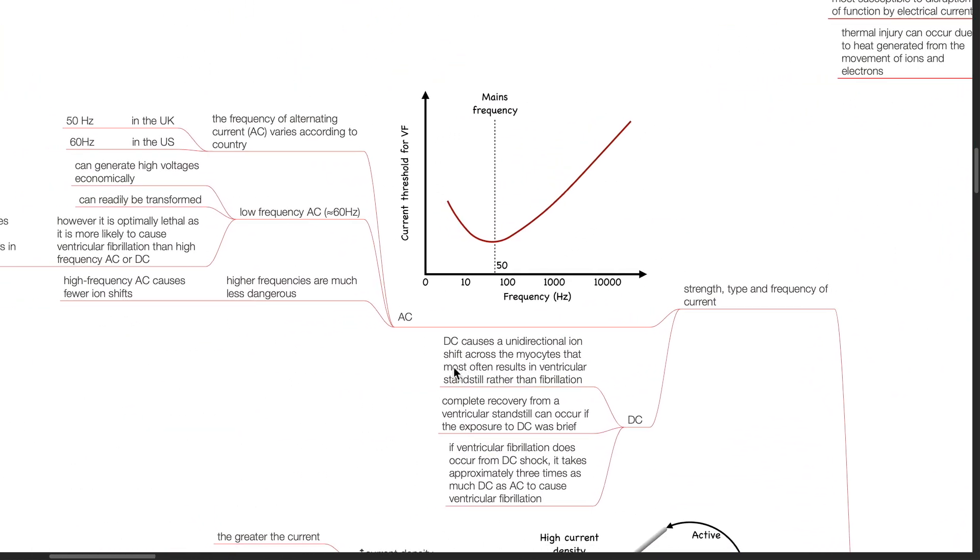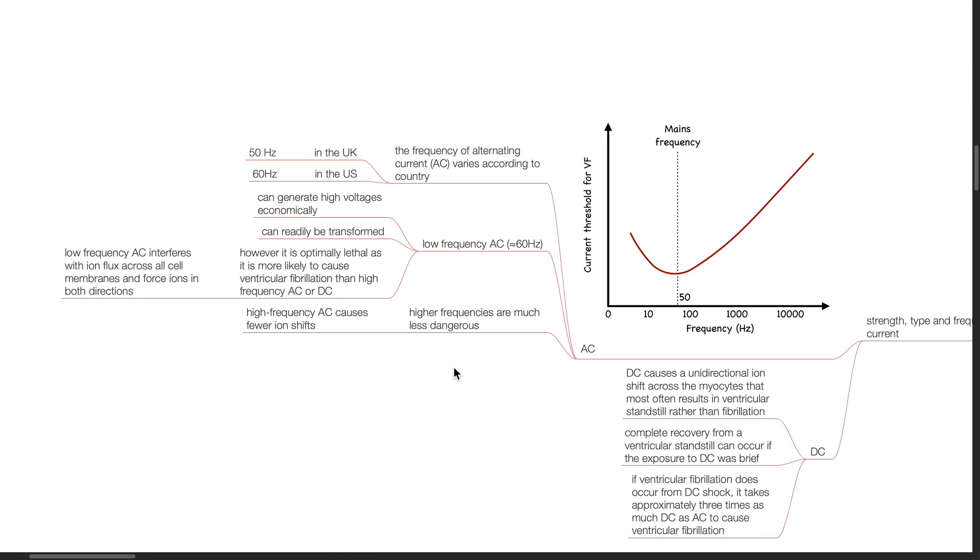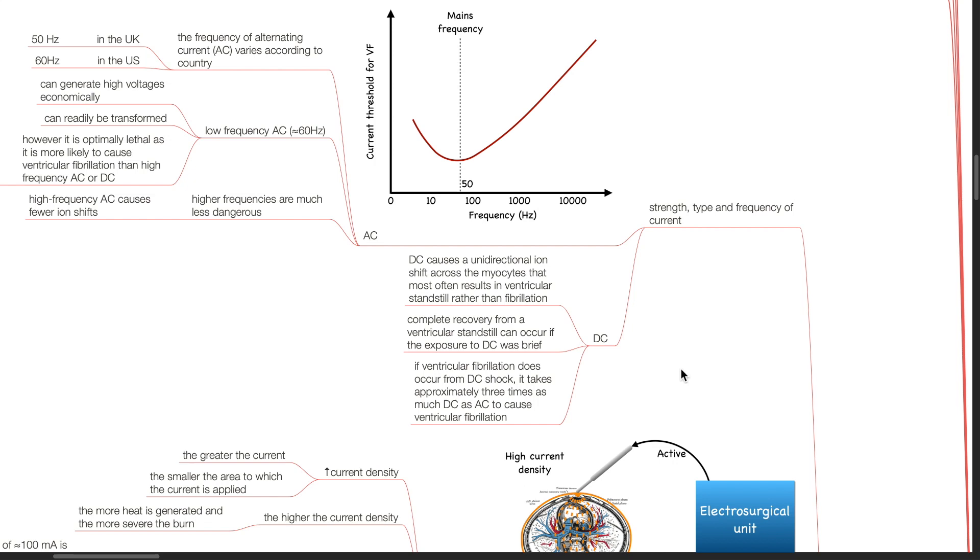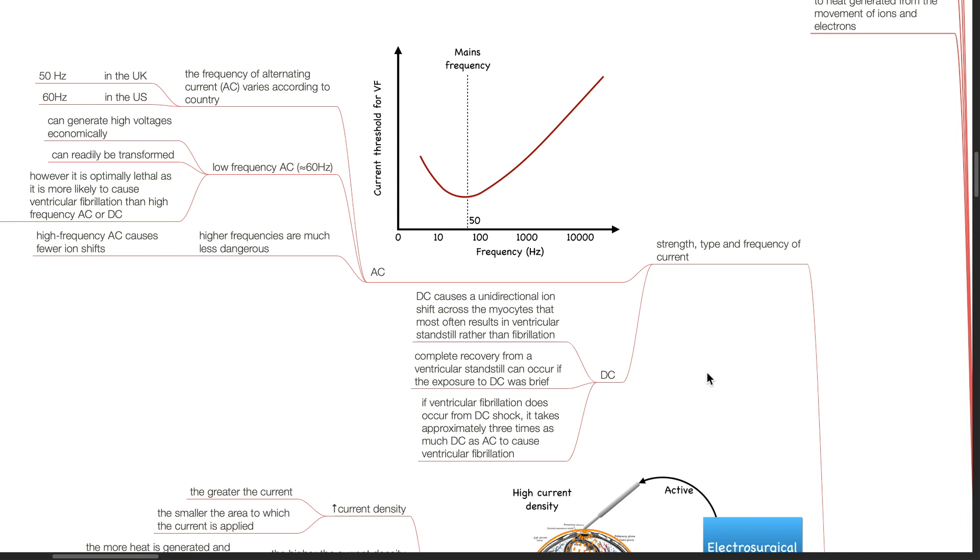The severity of macroshock depends on the strength, type and frequency of the current. For AC, the frequency varies according to the country, 50 Hz in UK and 60 Hz in US. Low-frequency AC, about 60 Hz, can generate high voltages economically and can be readily transformed. However, it is optimally lethal as it is more likely to cause ventricular fibrillation than high-frequency AC or DC. Low-frequency AC interferes with ion flux across cell membranes and forces ions in both directions. High-frequency AC are much less dangerous and cause fewer ion shifts.